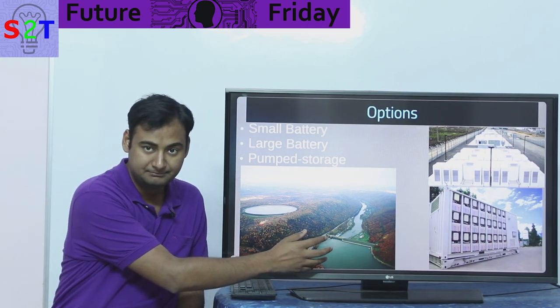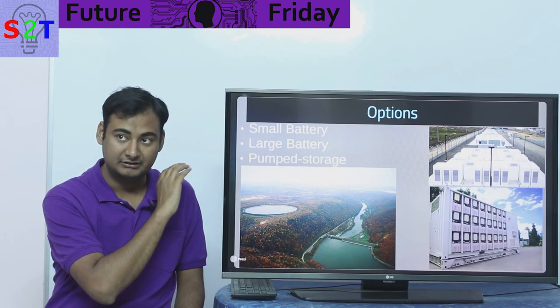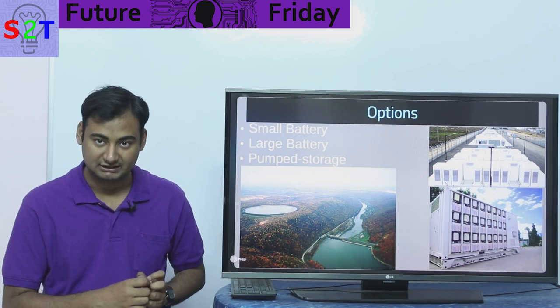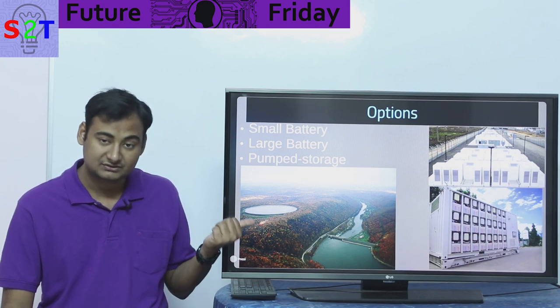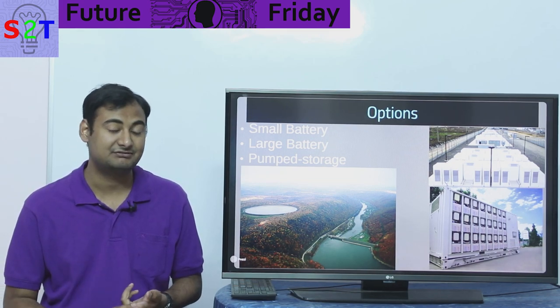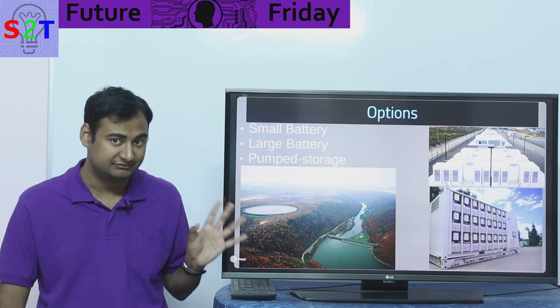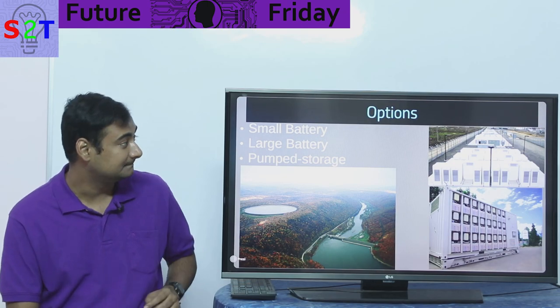The biggest storage system we have is called pumped hydro storage. You have a hydro dam that pumps water up to a reservoir — that's the charging phase. When peak demand hits and the hydro plant can't generate more power, it discharges the pond, and during that gravity-driven discharge you get extra electricity. This system generally starts at 1,500 to 2,000 megawatts, making it quite successful. However, you first need a location with abundant water and sufficient height variation — it's very location specific.